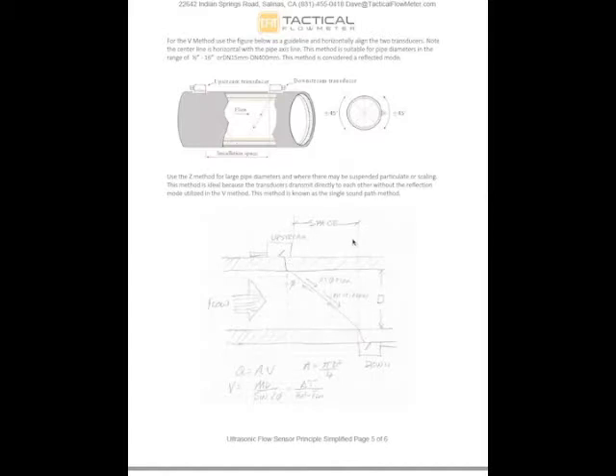So what's really important in this is that these transducers be spaced precisely apart from one another. If they're off, and where we can gain our claim of accuracy is based on how accurately we place these transducers. That's the advantage of this particular mounting structure, because a person can take a caliper, and the system will tell you what the distance must be based on this pipe diameter and this pipe thickness, so that the transit beams will go from one to the other. So that's the really important part.